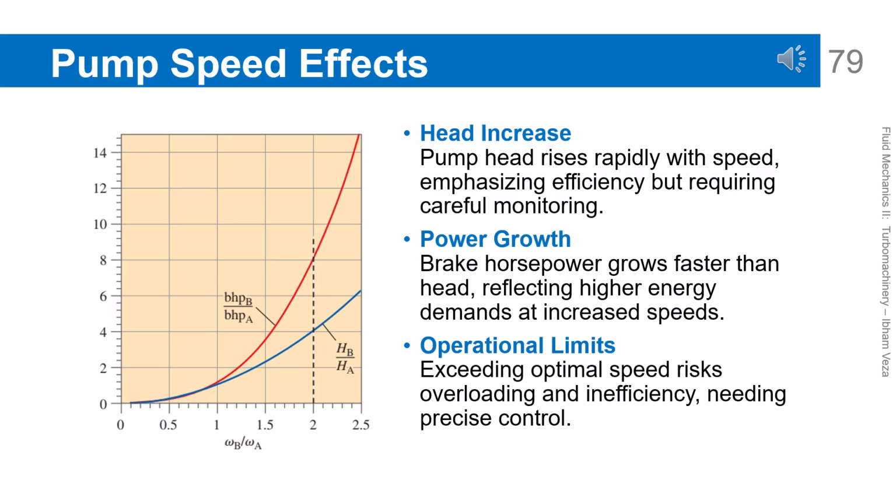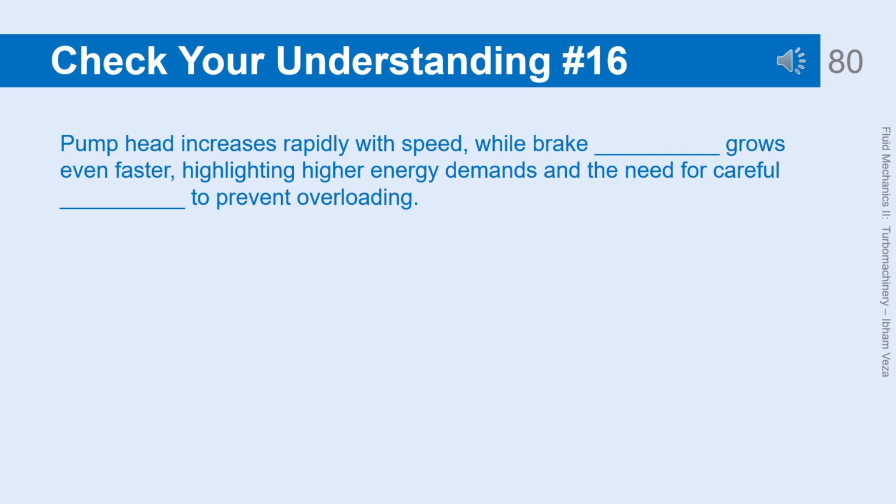This slide emphasizes the need for caution when increasing pump speed. Pump head increases rapidly with speed, while brake horsepower grows even faster, highlighting higher energy demands and the need for careful monitoring to prevent overloading.